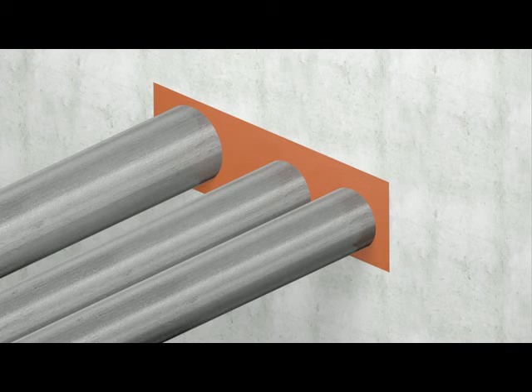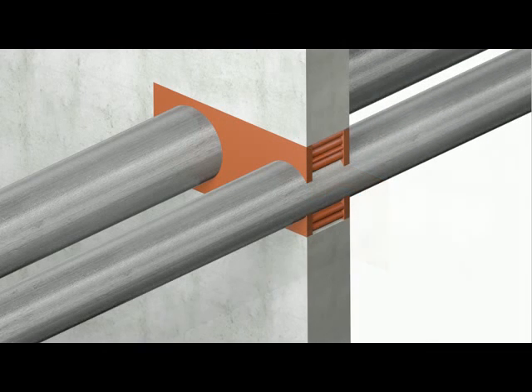For E120 class pipe penetrations, the minimum depth of the conduit is 150mm. For optimum fire safety, especially in the case of larger ducted pipes, we advise to use conduit depths of 200mm.